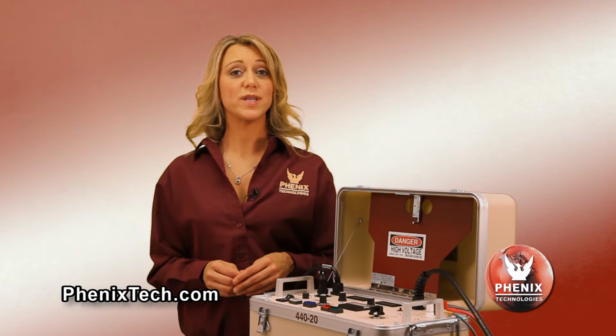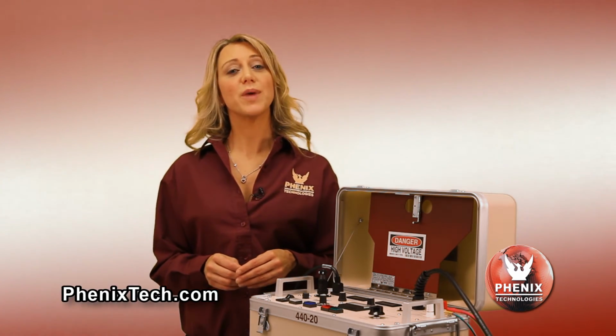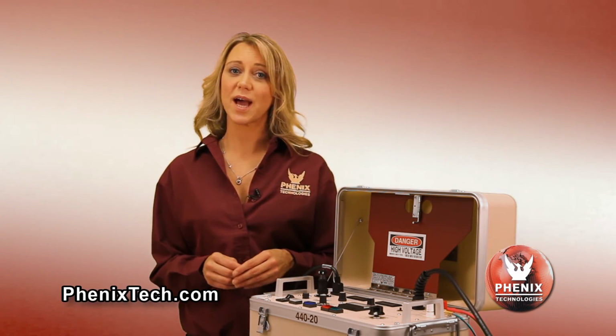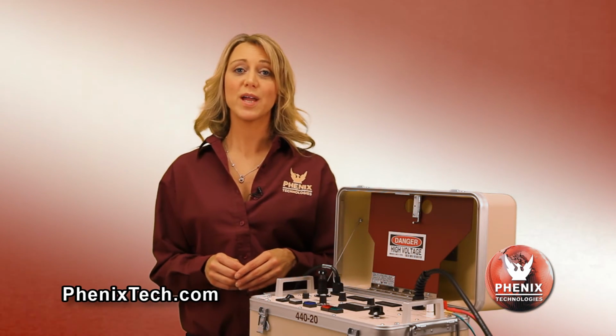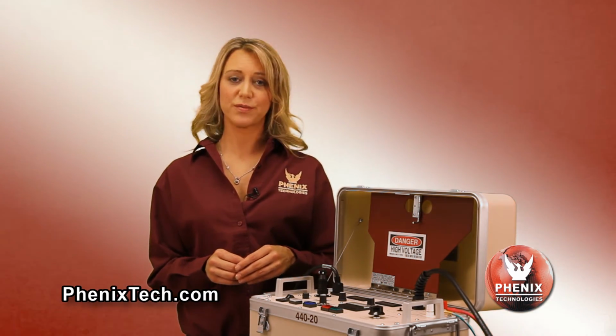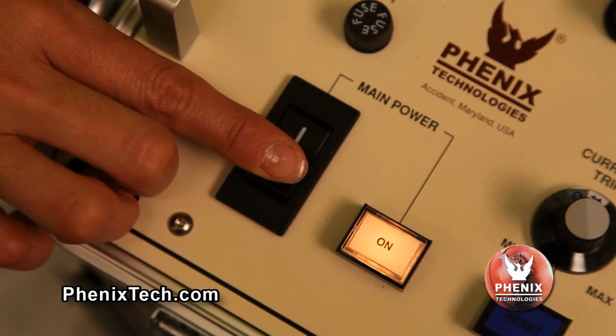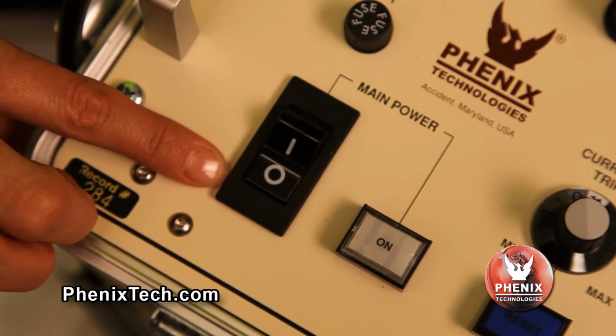Use the appropriate discharge or grounding stick to discharge the test object or allow the voltage to return to 0. The voltmeter will read any residual voltage that may be present on the test object's high voltage terminal with the Hipot output voltage turned off. After testing is completed, turn off the front panel main power switch. Make sure the test specimen is totally discharged and grounded before removing the test cables.